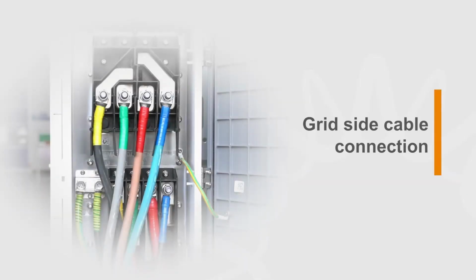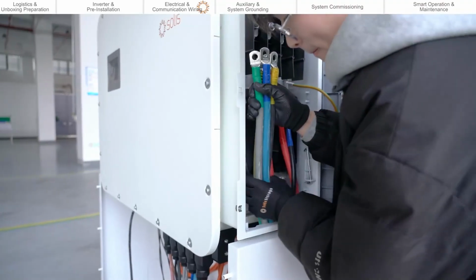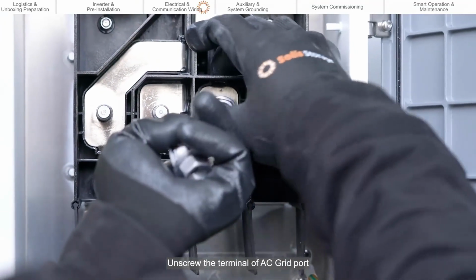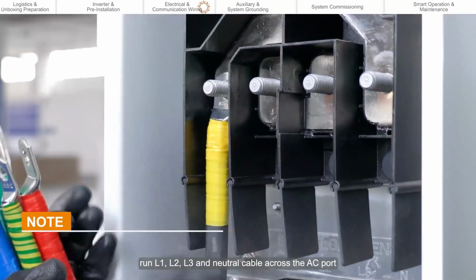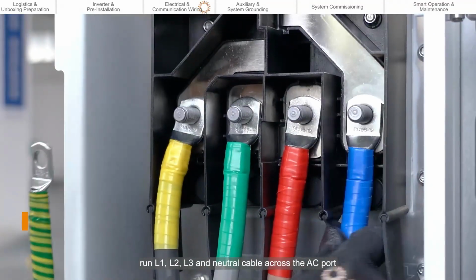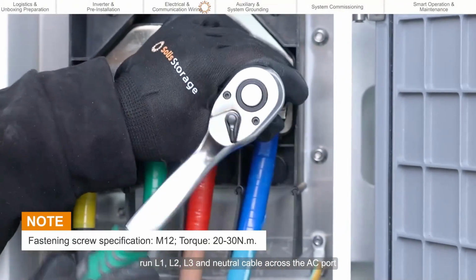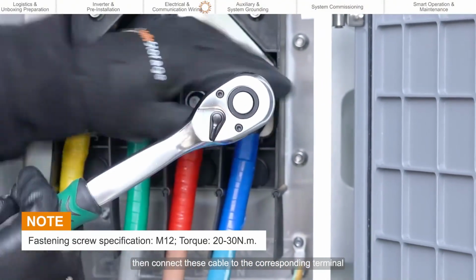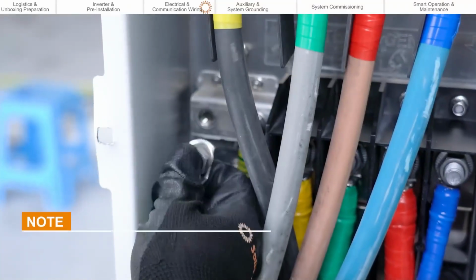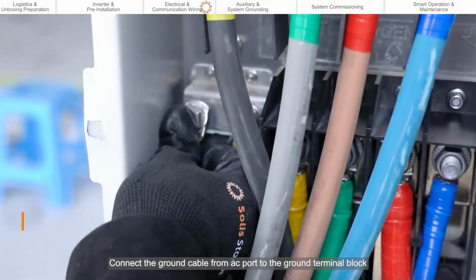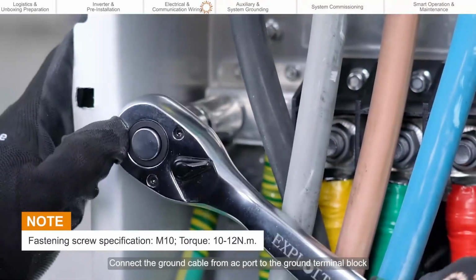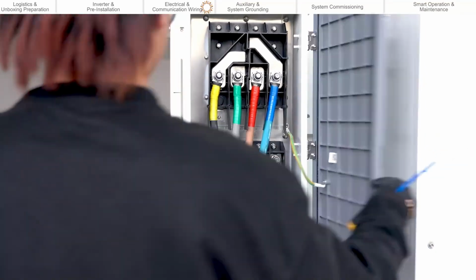Grid side cable connection. Unscrew the terminal of AC grid port. Run L1, L2, L3, and neutral cable across the AC port, then connect these cables to the corresponding terminal. Connect the ground cable from AC port to the ground terminal block. Close the AC junction box.